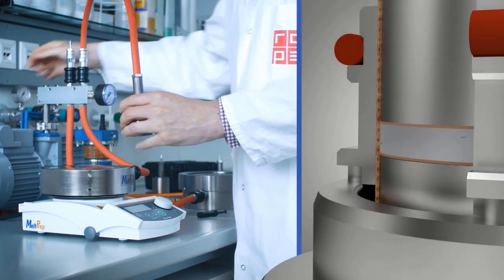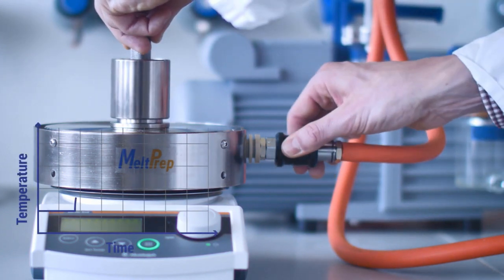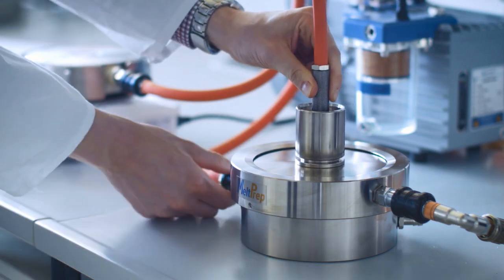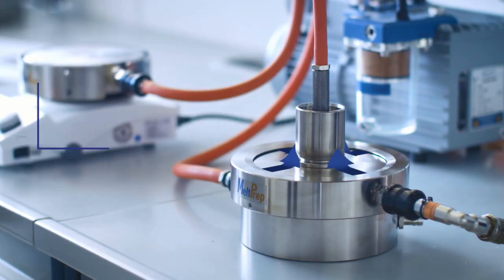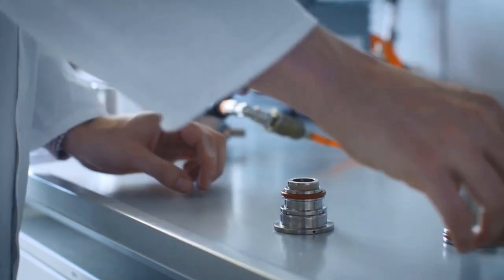After the VCM tool is connected to the vacuum unit, the air is drawn out and the powder is compacted. Subsequently, the VCM tool is placed on the hot plate to initiate melting. The powdery material forms a homogeneous melt — as a rule of thumb, this takes about five minutes. Once completed, the VCM tool is transferred to the cooling unit to cool down to ambient conditions. After cooling, it is taken apart and the sample can be released with ease. The PTFE foils can be peeled off like stickers.